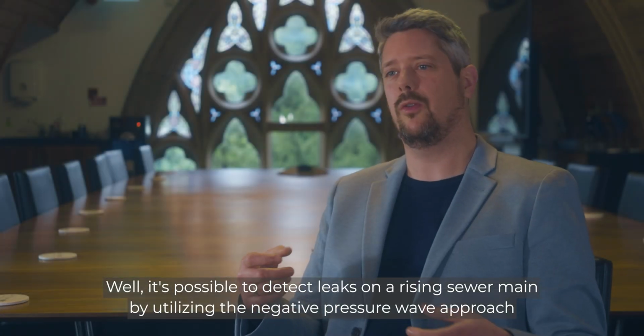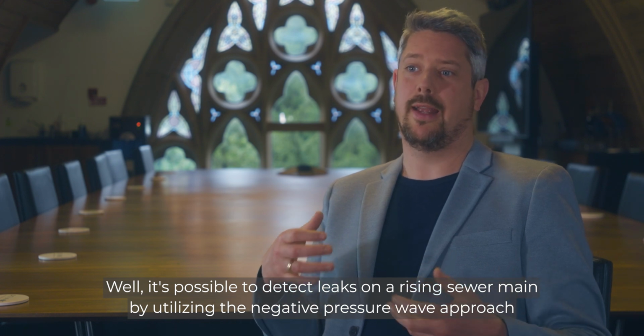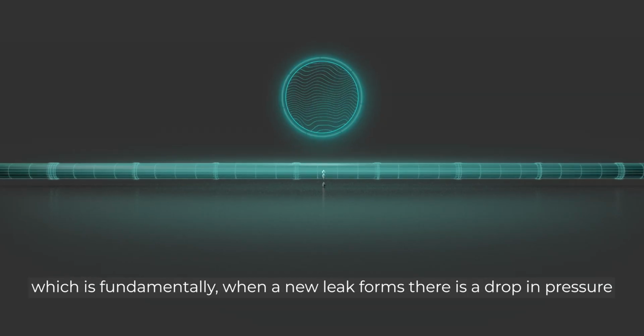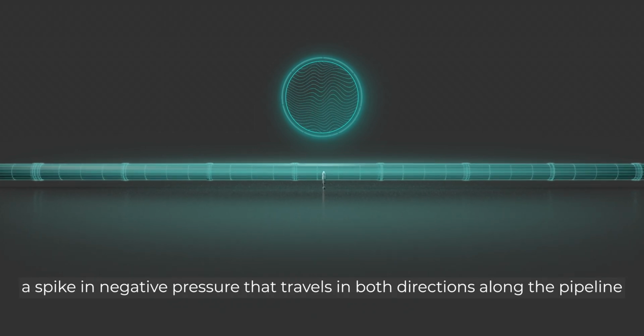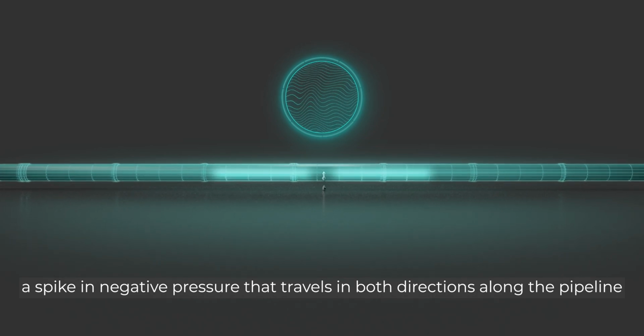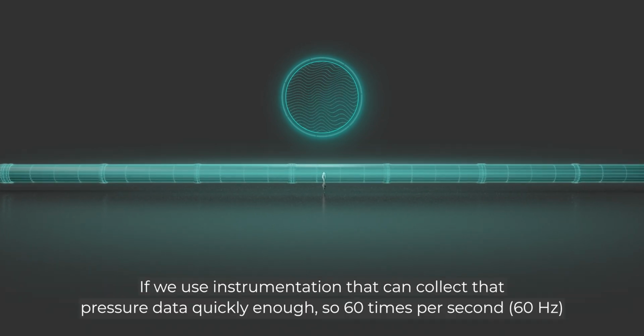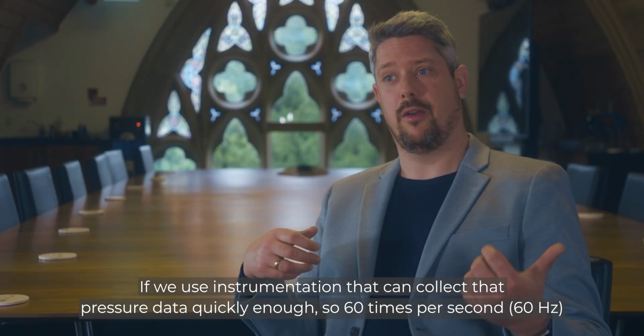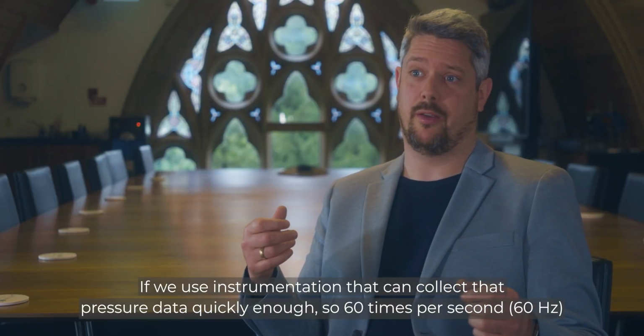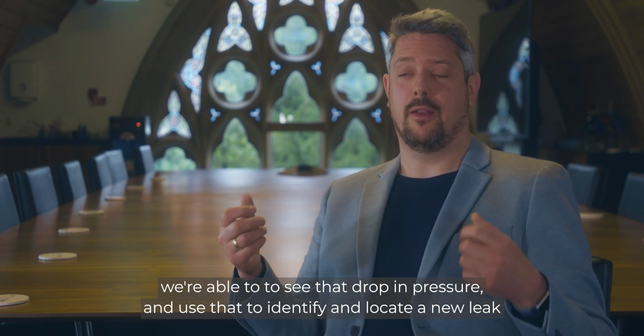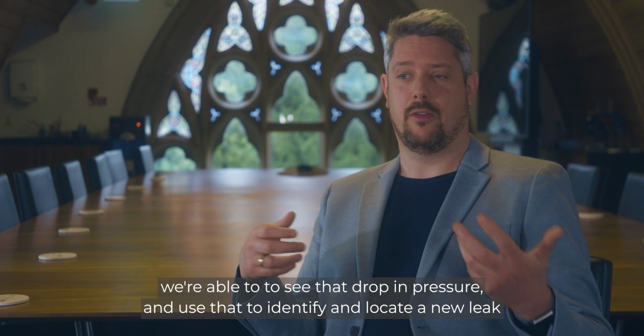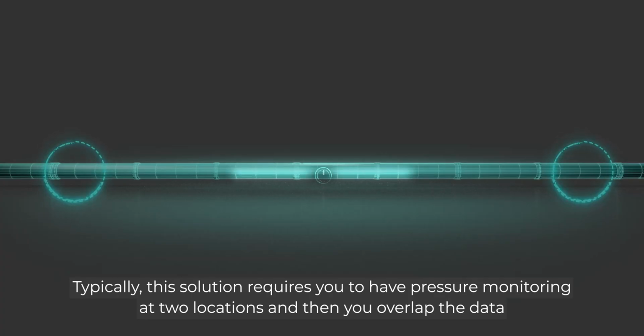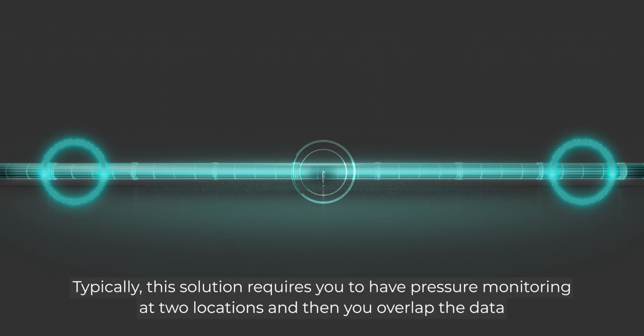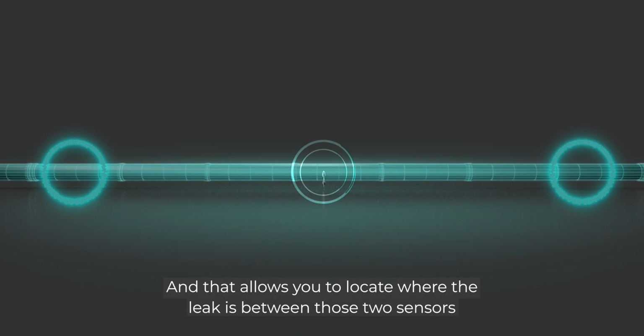Well, it's possible to detect leaks on a rising sewer main by utilising the negative pressure wave approach, which is fundamentally when a new leak forms, there is a drop in pressure, so a spike in negative pressure that travels in both directions along the pipeline. If we use instrumentation that can collect that pressure data quickly enough, so 60 times per second, we're able to see that drop in pressure and use that to identify and locate a new leak. Typically, this solution requires you to have pressure monitoring at 2 locations, and then you overlap the data, and that allows you to locate where the leak is between those 2 sensors.